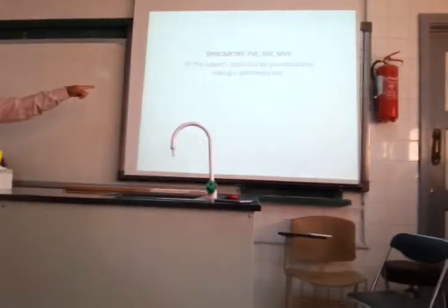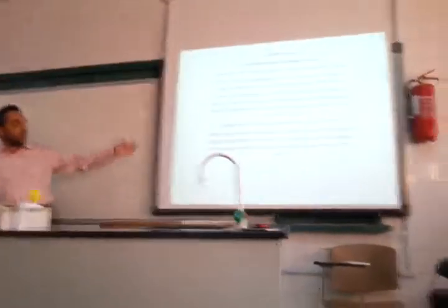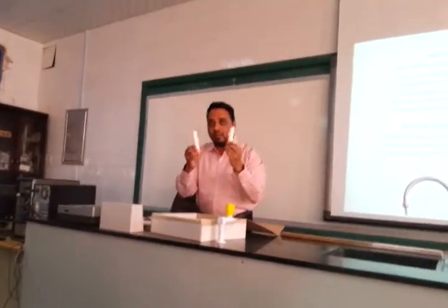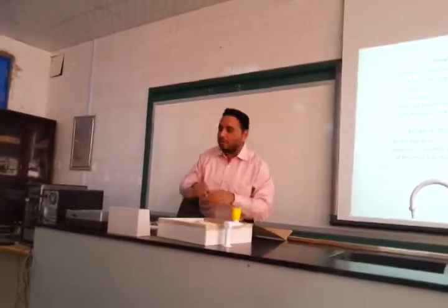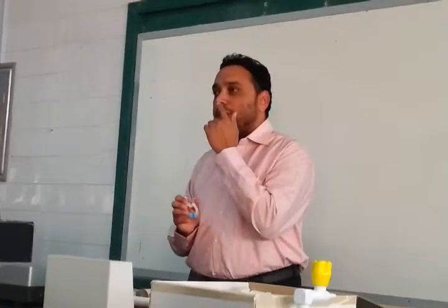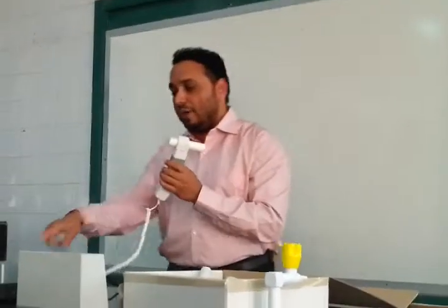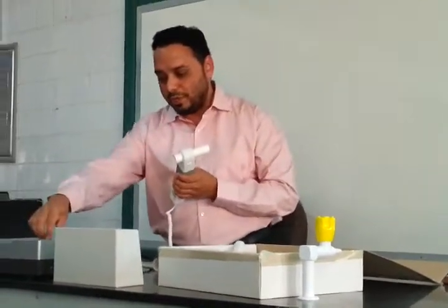All subjects' data must be inserted into the machine before making a spirometry test. Now there is a box here, and here are the mouthpieces, and there is something called a nose clip. You can use it to pinch the nose. Why? You don't want leakages. You don't want air to leak out from the nose. The mouthpiece is attached here. After you do it, you start the system.